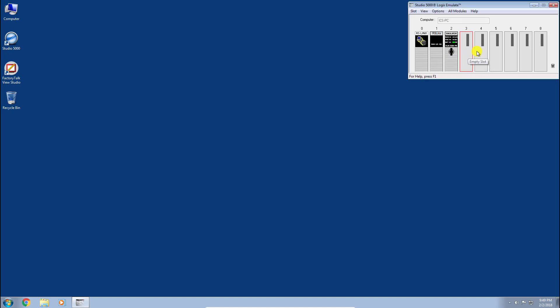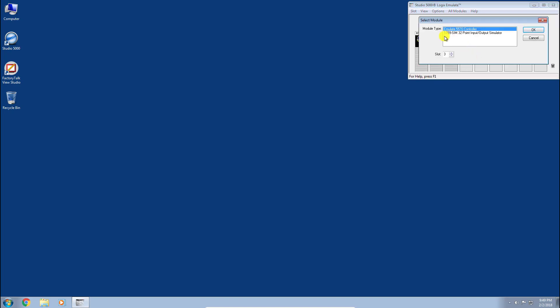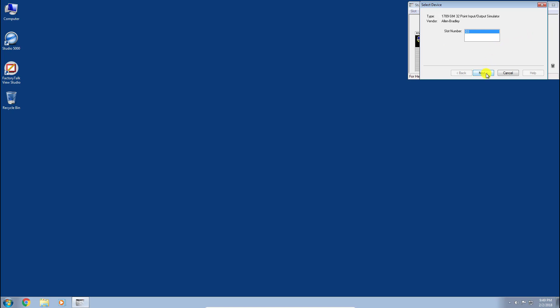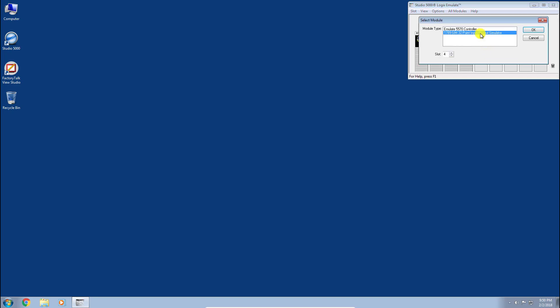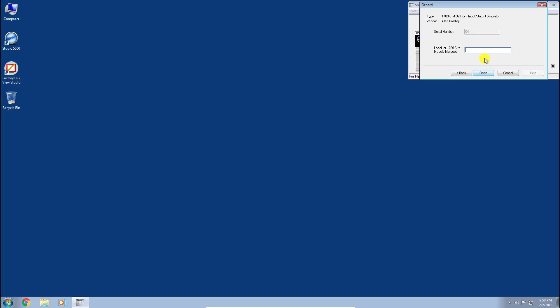Next, let's add a couple of IO modules. I'll right-click on slot 3 and click Create. I'm going to select the 1789 Simulation Module — it's a 32-point input/output simulator that can simulate an input module, an output module, or a combination of both. We'll configure two: one acting as an input module and the second as an output module. I'll click OK, put it in slot 3, and label it 'Inputs' for the marquee. You can see it's now scrolling 'Inputs' across the module.